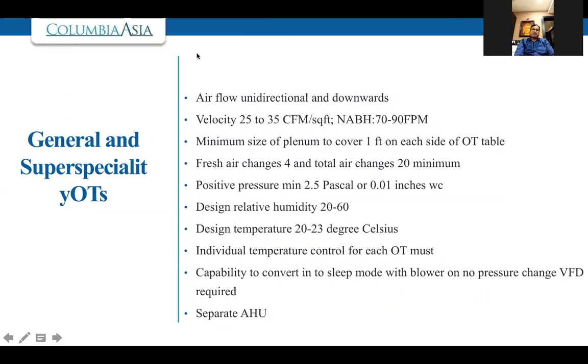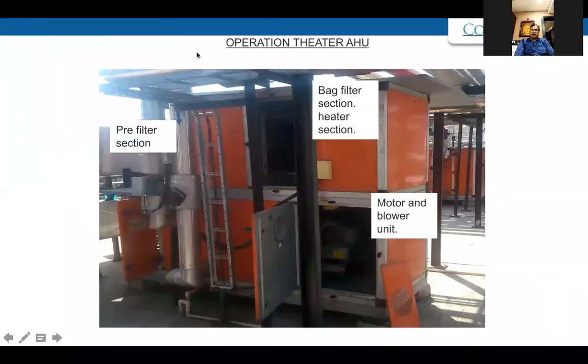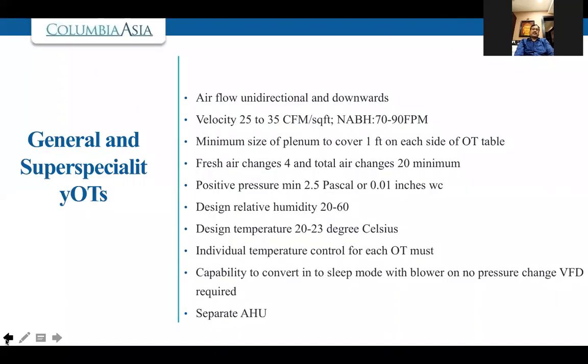Another very important aspect which generally nobody follows, very few hospitals follow, is the VFD, variable frequency drive, which means that you are allowing the blower to be on all the time. And this actually increases the expenditure. That's why most of them shut down the OT-AHU completely. But whereas they need to put it in sleep mode, whereby the blower will always be on.